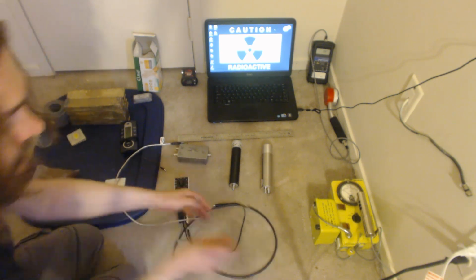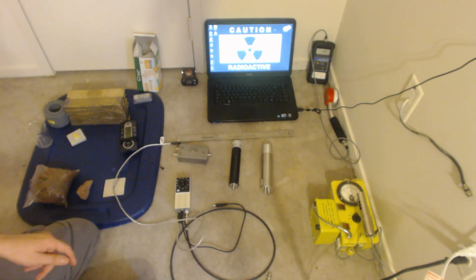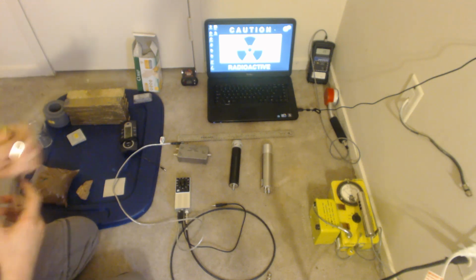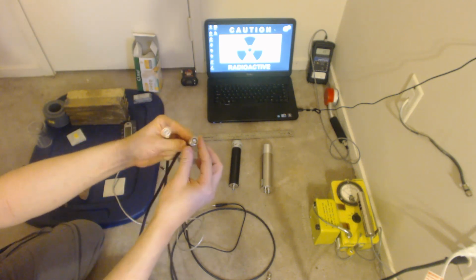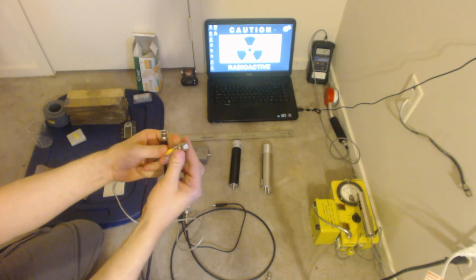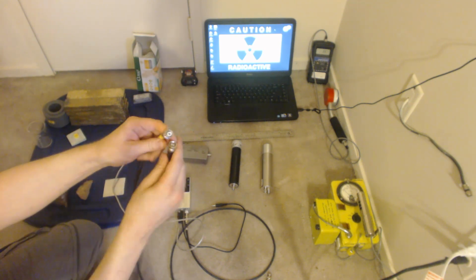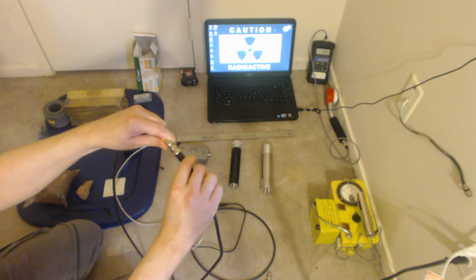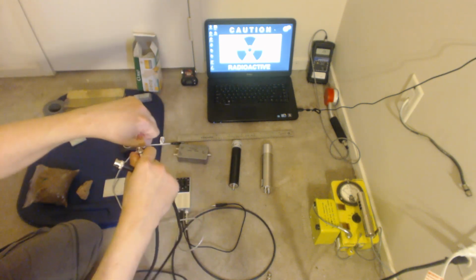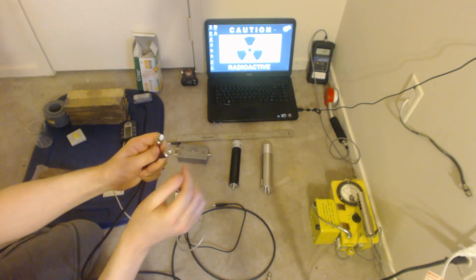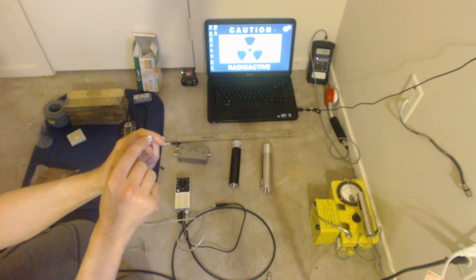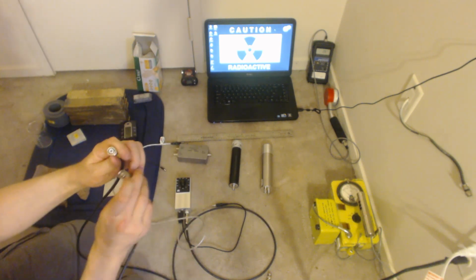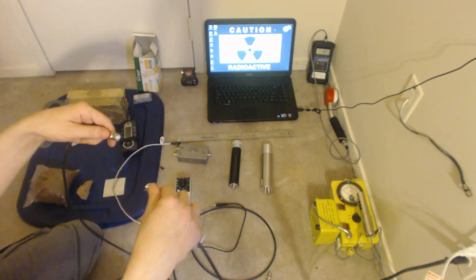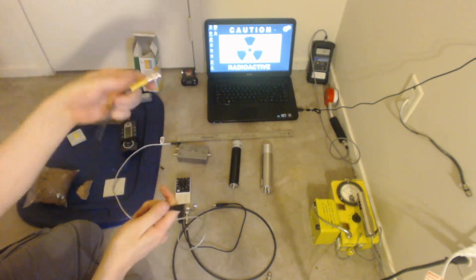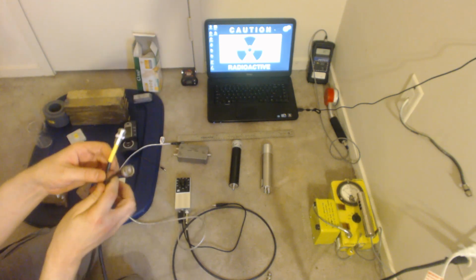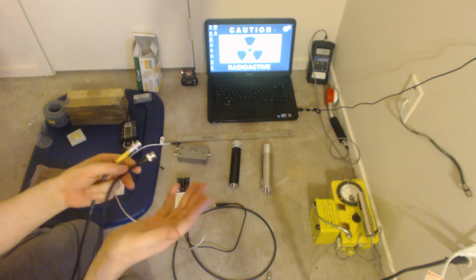The other thing to know about is the actual connectors themselves. Let me see if I can get you an example. Here we go. The two types of cables you'll deal with: BNC cables, miniature high voltage cables. They are nearly the same, but they're not quite. They go on and they twist, same sort of way, but the difference is this one has a slightly larger piece, the little white piece in the middle here. It's extended a little farther than this piece is, and they don't quite fit onto one another. This is designed for higher voltage than this is, although quite frankly they're nearly interchangeable.